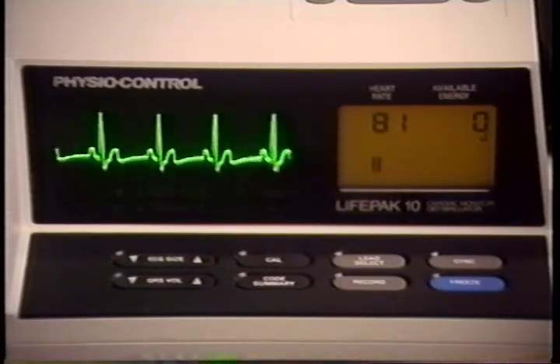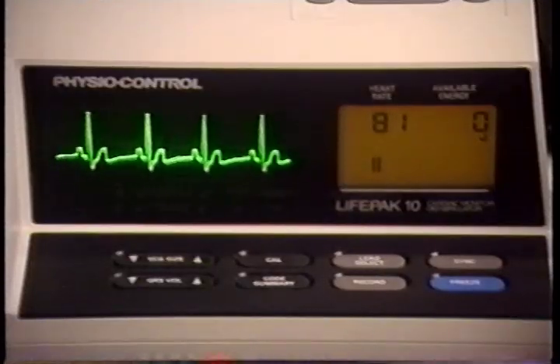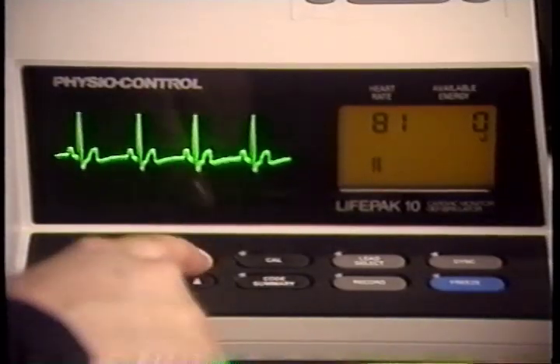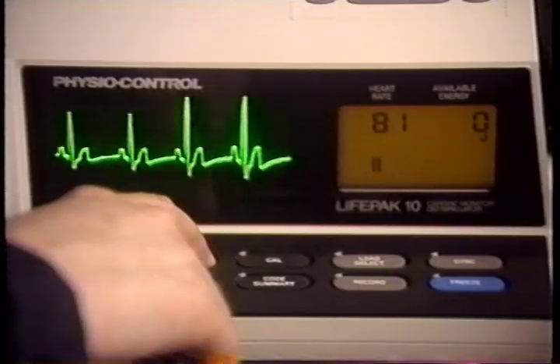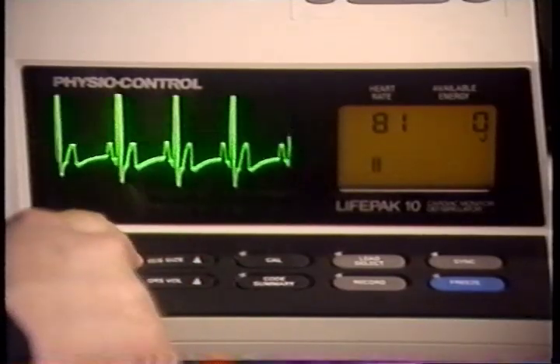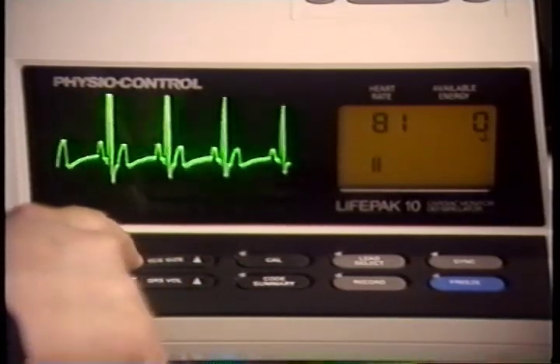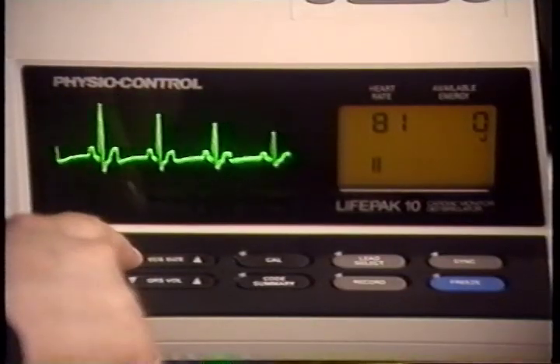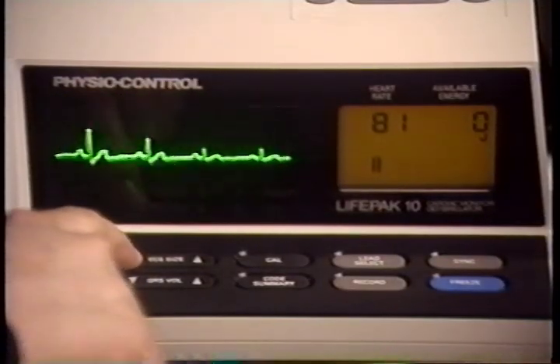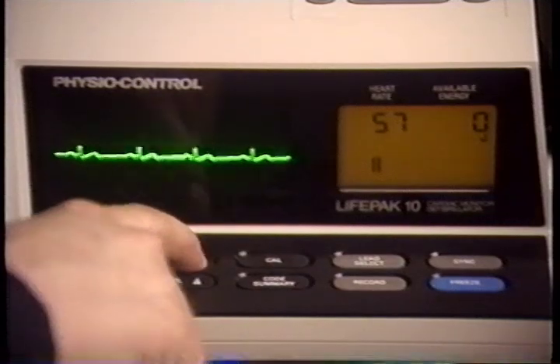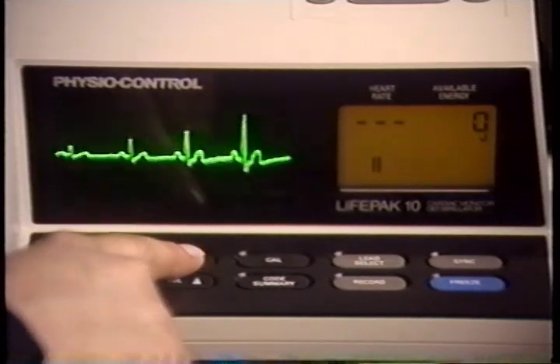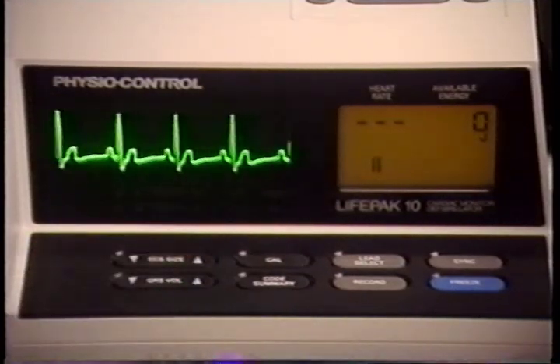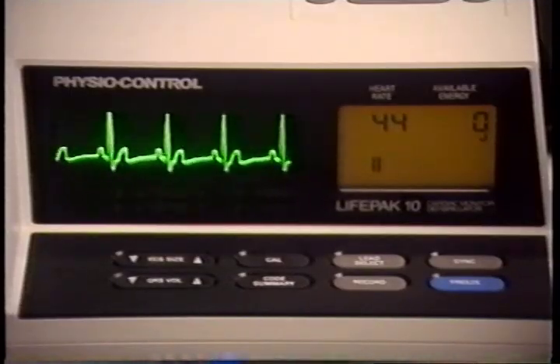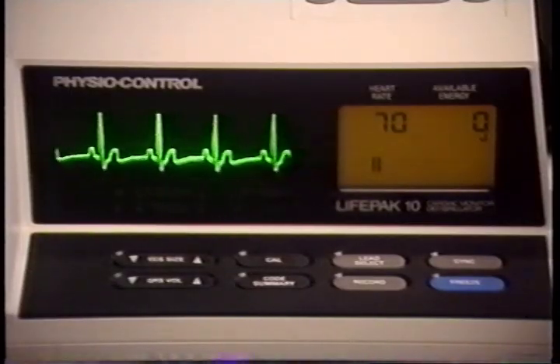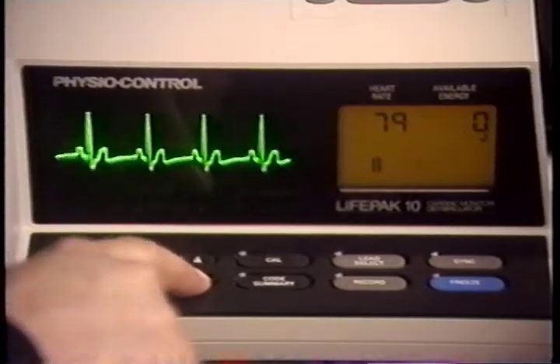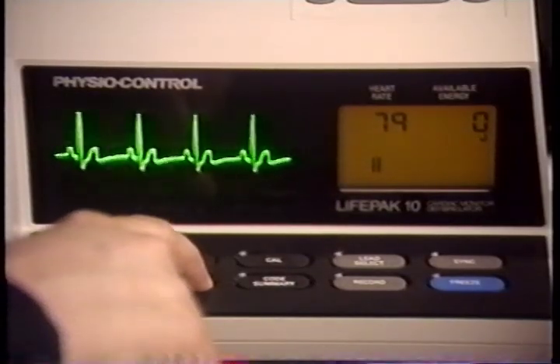The size of the ECG signal can be increased or decreased by pushing the ECG size button. Push the right side of the button to increase the ECG size and push the left side to decrease it. When you reach the upper or lower limit of the ECG size adjustment, 3 tones will sound. ECG size is documented on the strip chart recorder. The QRS volume control powers up at minimum volume. Push the right side of the button to increase the QRS volume and push the left side to decrease it.